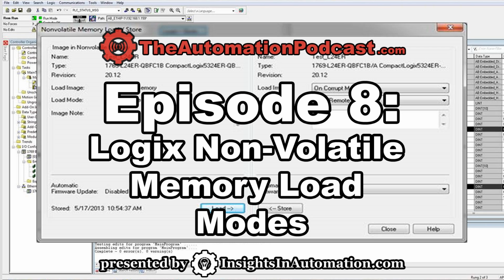So once the processor is done storing our program to the non-volatile, we'll want to go back online and download program 2. Now with program 2 downloaded to the controller, because we set the non-volatile memory to load on power up, when we cycle power, it should load program 1 back into memory. So let's go ahead and cycle power to the controller, reconnect, and verify again program 2 has been wiped out and program 1 is back into memory.